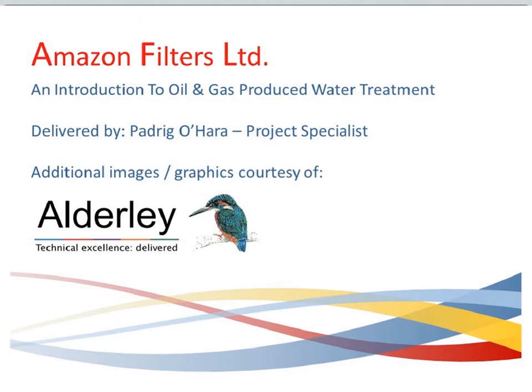But the suitable technologies change very rapidly once we start looking at a low volume of water, perhaps a couple of cubic meters an hour, versus the 800 to 900 cubic meters an hour plus we can be processing offshore or onshore in an oil field produced water application. So it's reverse osmosis technologies and cartridge filters, and even for removing oil, absorptive cartridge filters offer a compact solution, because you're not dealing with a big volume of water. You're looking at a system that's compact and relatively cheap to install, less concerned about the OPEX per barrel or per cubic meter treated.